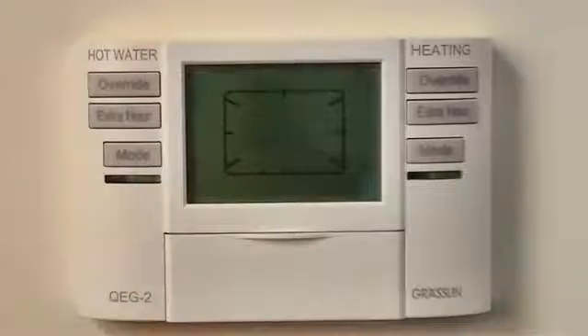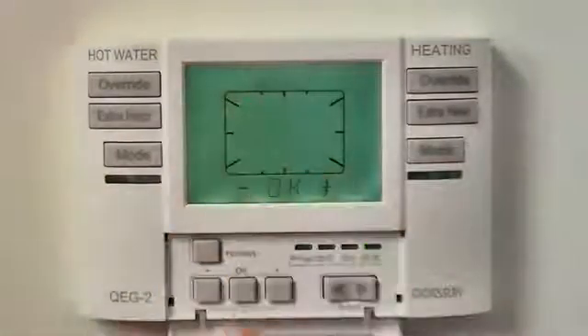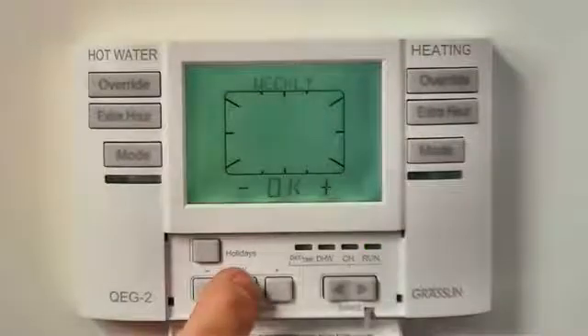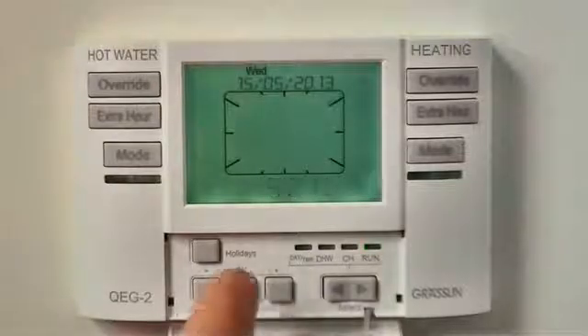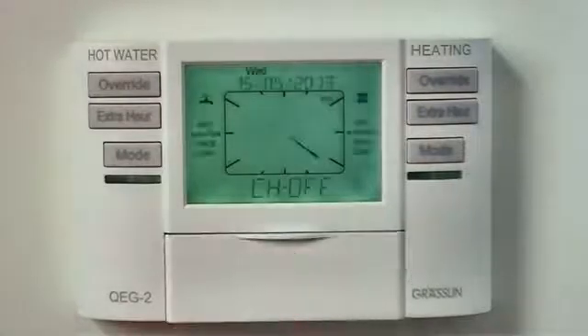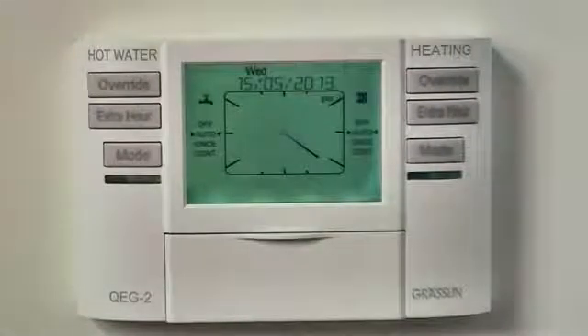The Grässlin QEG2 is a new user-friendly heating and hot water programmer. Setting up your new QEG2 is really easy. Switch on the mains power, open the cover and press the OK button three times. This confirms the programming style, the date and the time. The inbuilt standard program is now running.